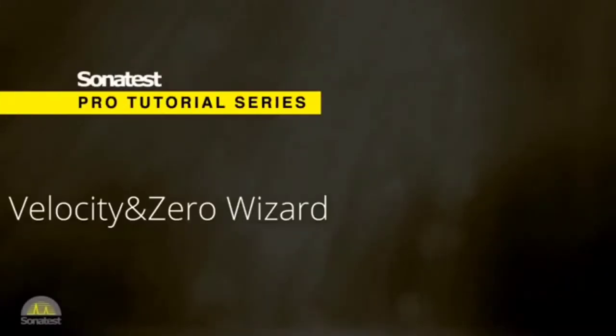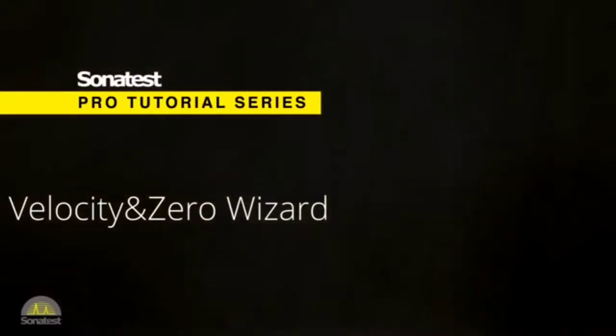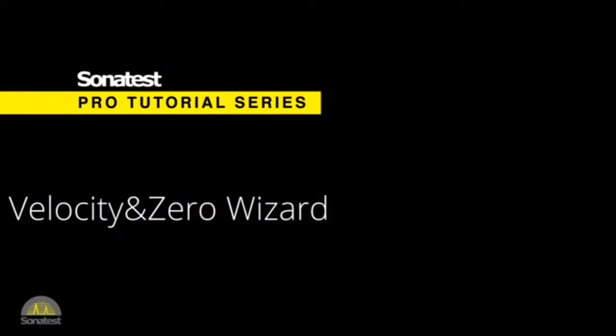Hello everybody. Today's tutorial is about velocity and zero calibration. This calibration is setting the speed of sound value of the calibration block material and the appropriate delay 0 for the beam used in the calibration.